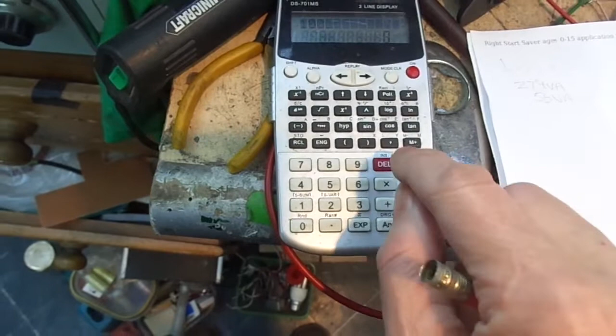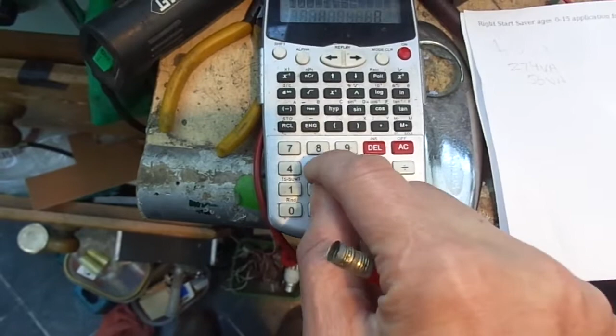56 VA. We go through the whole amp. We're going to need a bias winding, so we're aiming for something like, from experience because I know it works, 100 volts DC. We divide that by 1.35 to get 74. We don't really need to bung 20 volts on that, maybe another 10, so let's say 84 volts. Let's just say 80 volts.